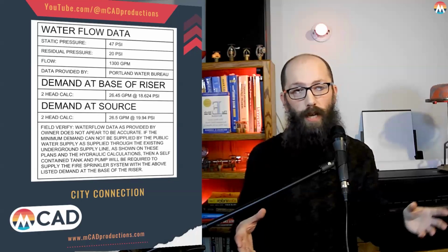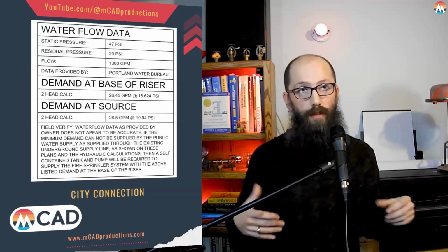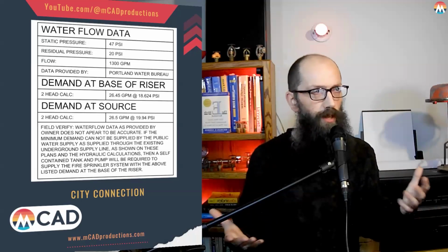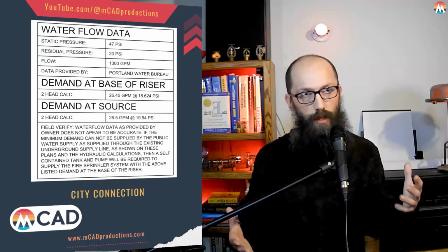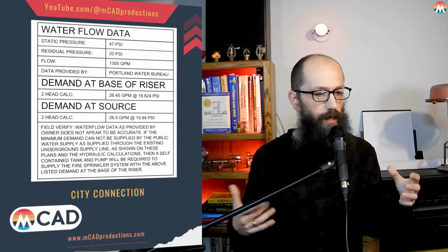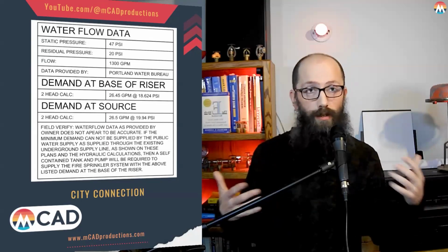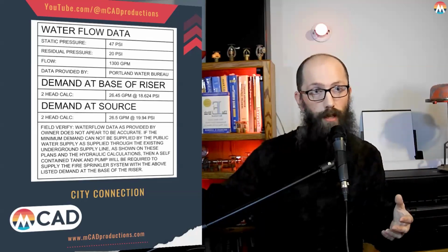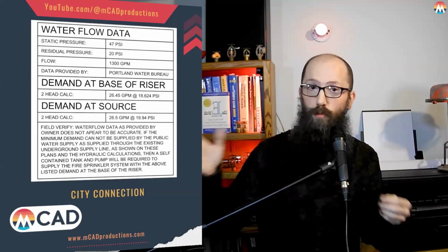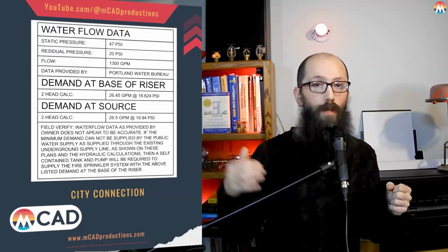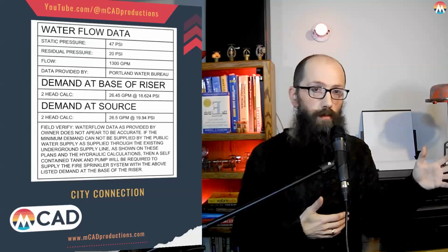the houses that we're doing have existing water lines, and they're existing houses that are getting sprinkler systems because things like they're taking a house and turning it into a daycare, or they're taking a house and putting it into an adult foster care home. And so it's an old house. It already has a water line. They tell us the info about it. We calc it. It works based off of what they told us. But a lot of times it doesn't match up.